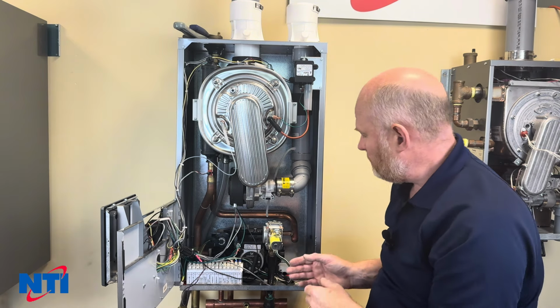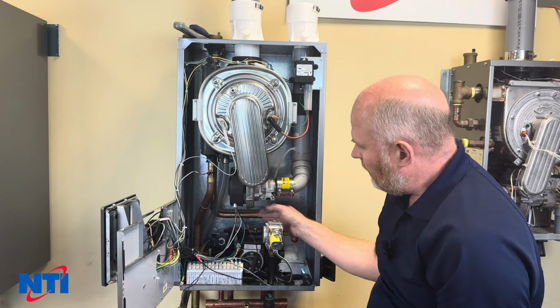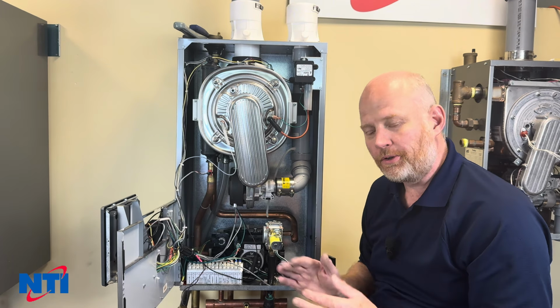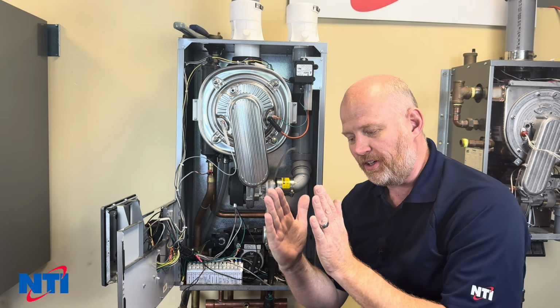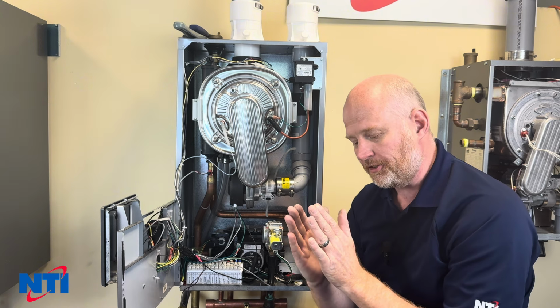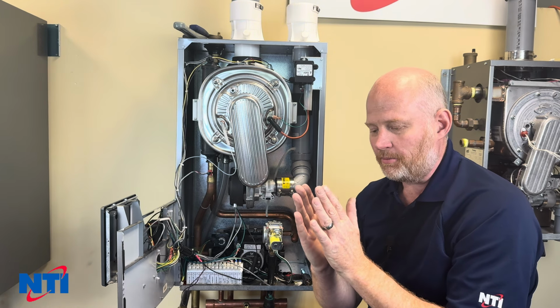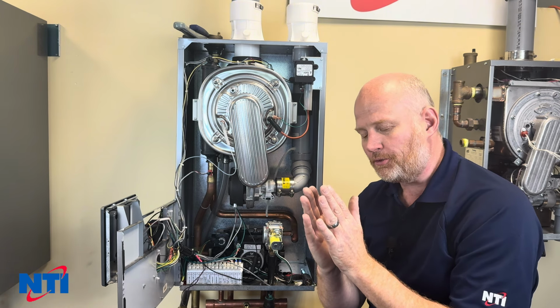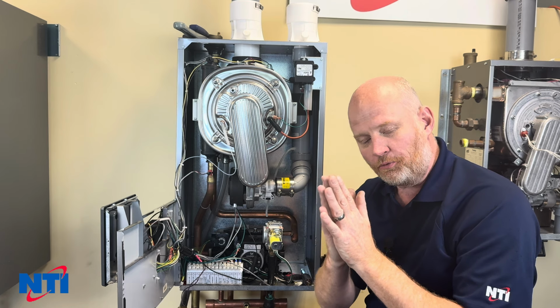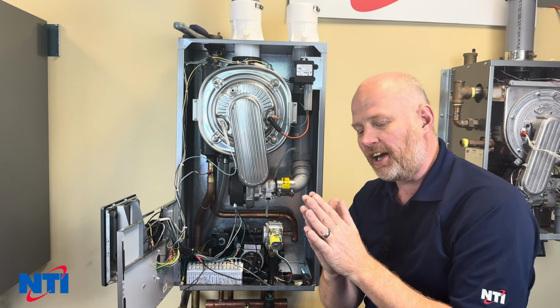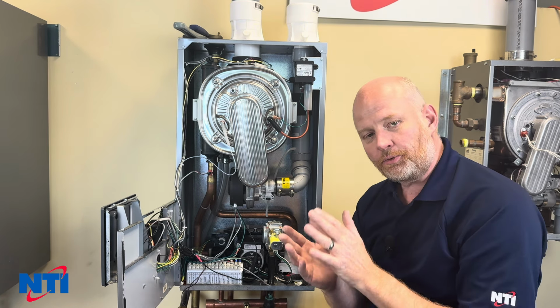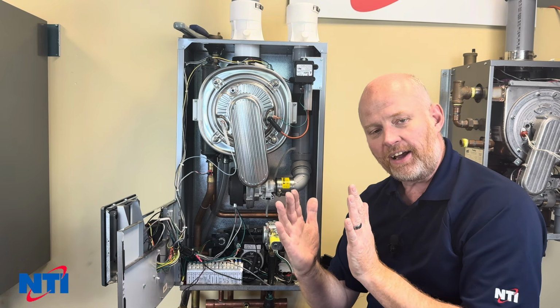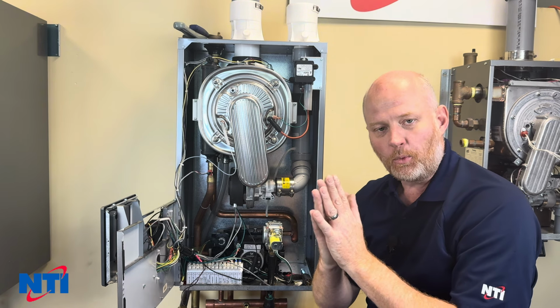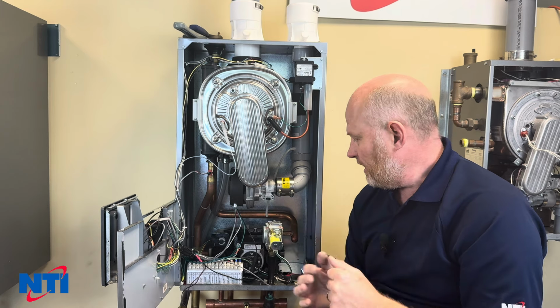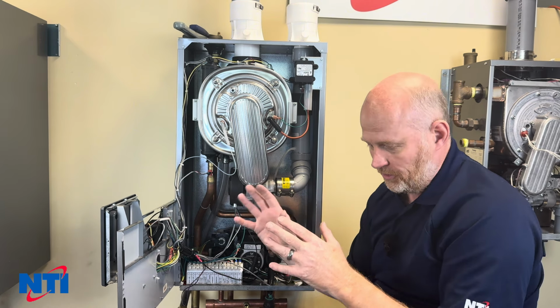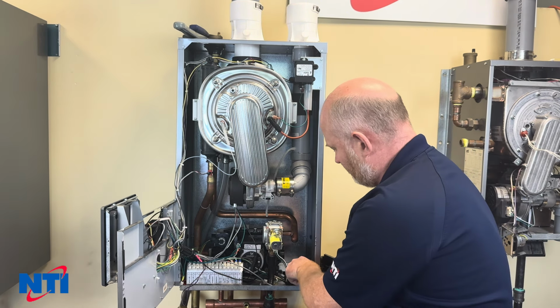Now the plate's back in, we can reinstall our gas valve. When you're tightening these down, remember they are sealed by a gasket. You're going to feel the gasket compress as you tighten the screw. Once the screw becomes tight, you'll notice it gets very stiff all of a sudden. Once that happens, you've fully compressed the gasket. Tightening it any more beyond that just runs the risk of breaking something. So you're going to have to do this by feel, but you're going to snug it up. Once the screwdriver gets very stiff, stop turning. Any more than that will tend to want to crack the plastic.